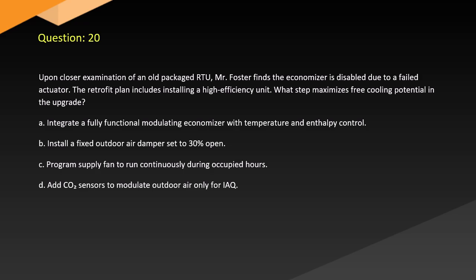Question 20. Upon closer examination of an old packaged rooftop unit, Mr. Foster finds the economizer is disabled due to a failed actuator. The retrofit plan includes installing a high-efficiency unit. What step maximizes free cooling potential in the upgrade? A. Integrate a fully functional modulating economizer with temperature and enthalpy control. B. Install a fixed outdoor air damper set to 30% open. C. Program supply fan to run continuously during occupied hours. D. Add CO2 sensors to modulate outdoor air only for IAQ.